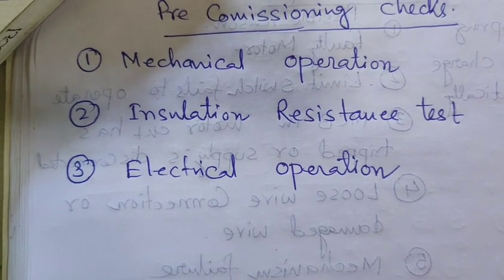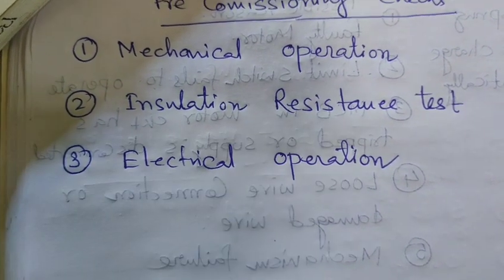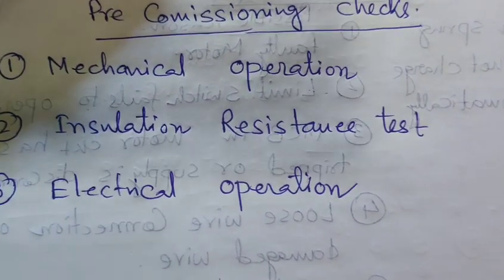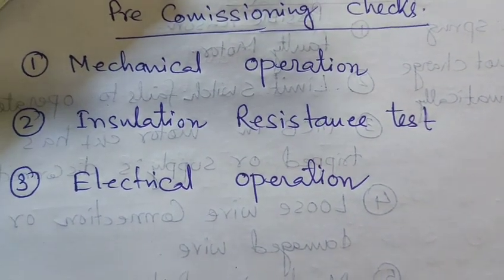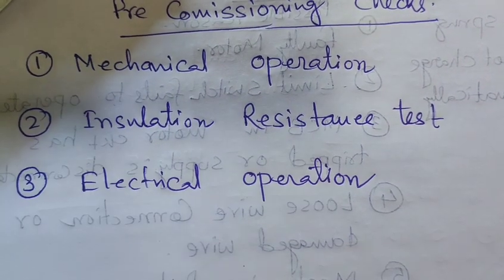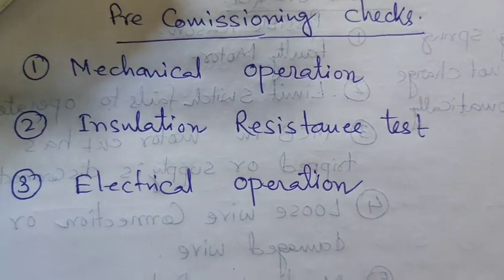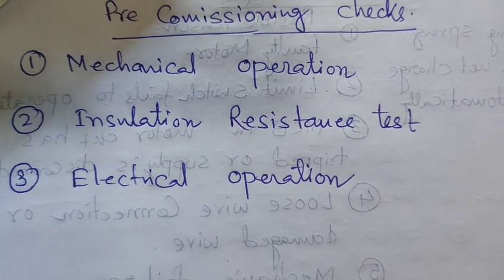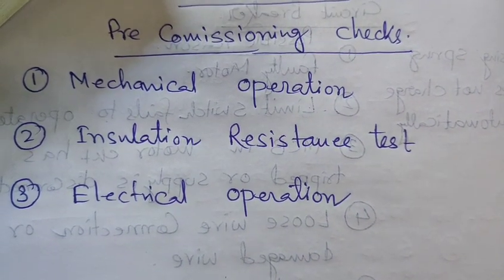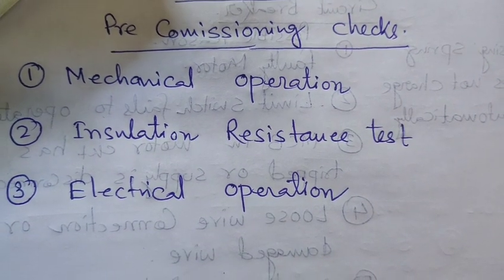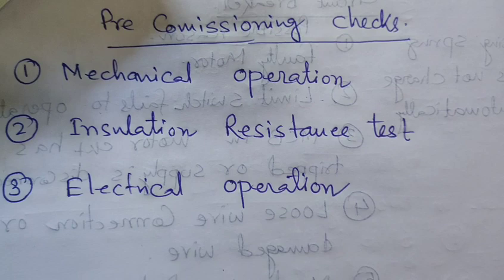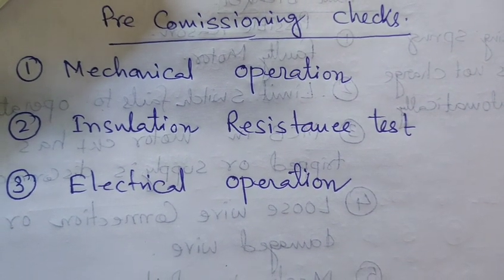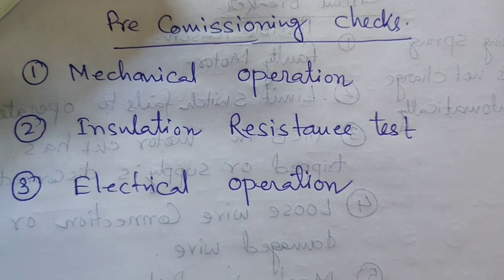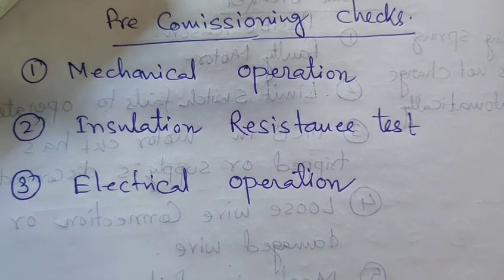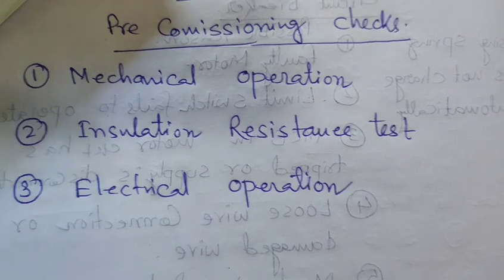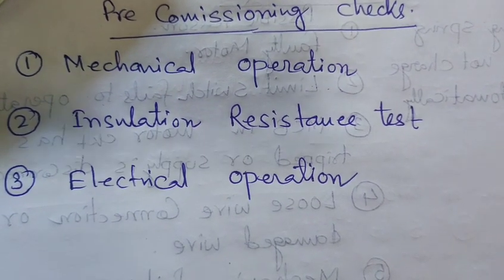It is 100 mega ohm. Above the 100 mega ohm it is good for the operations. If it is below the 100 mega ohm, it should be consulted with the concerned testings and the HV test. What type of HV test? Power frequency high voltage resistance test. The power frequency high voltage resistance test should be done on this circuit breaker to ensure that the circuit breaker is suitable for operations at the 36 kV sustaining voltage.